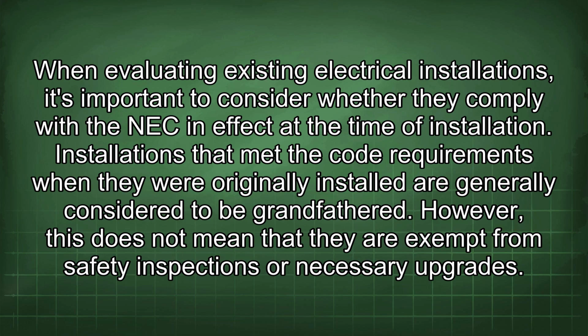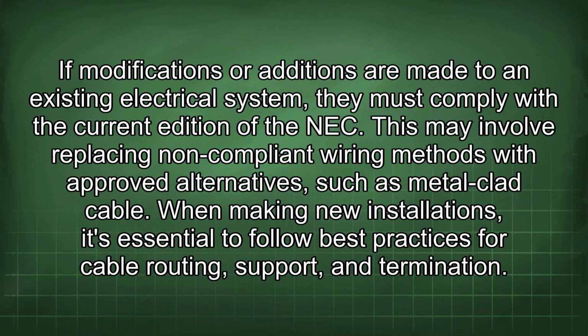Installations that met the code requirements when they were originally installed are generally considered to be grandfathered. However, this does not mean that they are exempt from safety inspections or necessary upgrades. If modifications or additions are made to an existing electrical system, they must comply with the current edition of the NEC. This may involve replacing non-compliant wiring methods with approved alternatives, such as metal-clad cable.